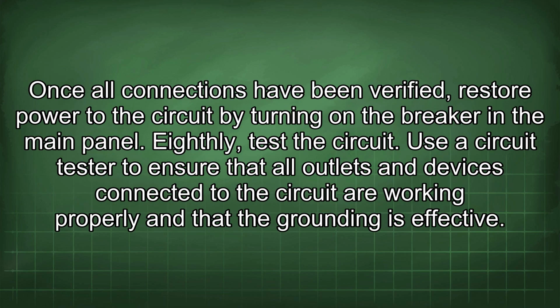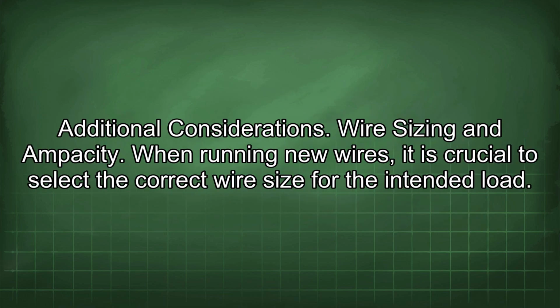Once all connections have been verified, restore power to the circuit by turning on the breaker in the main panel. Eighthly, test the circuit. Use a circuit tester to ensure that all outlets and devices connected to the circuit are working properly and that the grounding is effective. Additional considerations. Wire sizing and ampacity. When running new wires, it is crucial to select the correct wire size for the intended load.